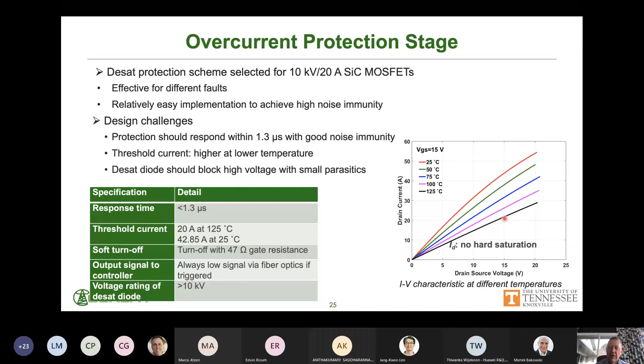A few more details on the Desat protection. This is showing here, we put several diodes in series to accommodate that 10 kilovolts. We didn't have a 10 kilovolt diode, so we put 4 3.3 kilovolt diodes here. We also needed some blanking time so that we don't, again, have false triggering during the turn on. We figured we needed more than 500 nanoseconds, so we ended up with about a 600 nanosecond minimum blanking time. And in addition to that, we ended up with about a 1.22 microsecond blanking time that we used. You can change it if you want, of course. If you want a shorter response time, you can just change your RC circuit and change that as you see fit.